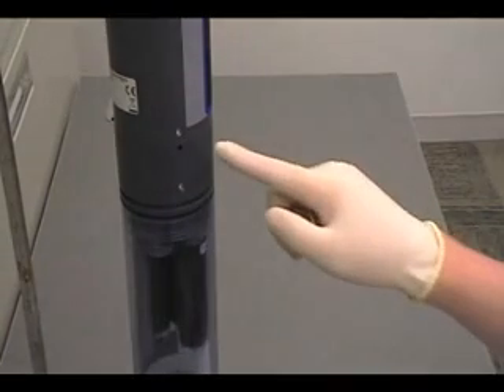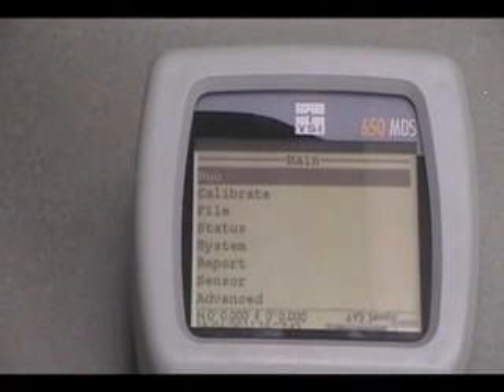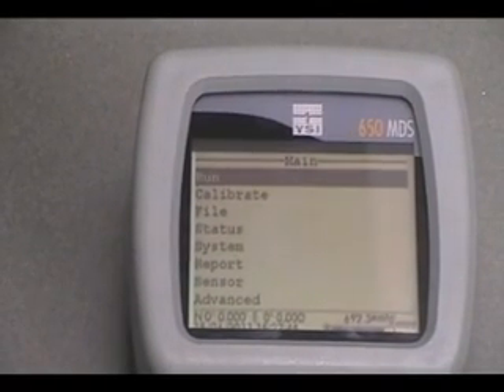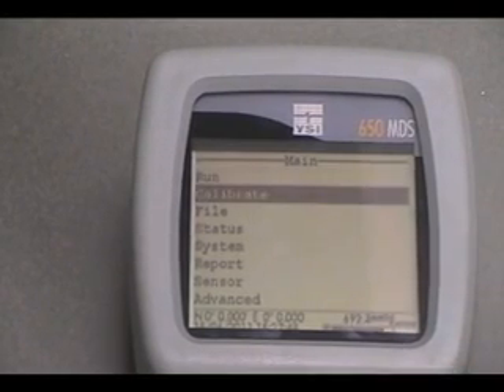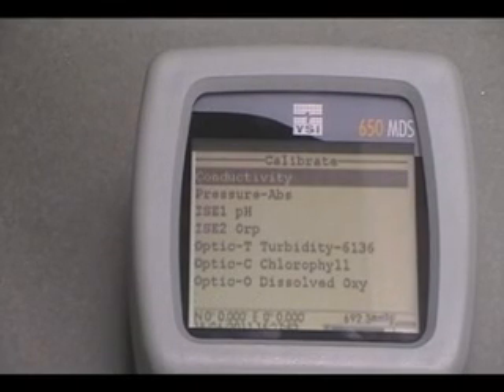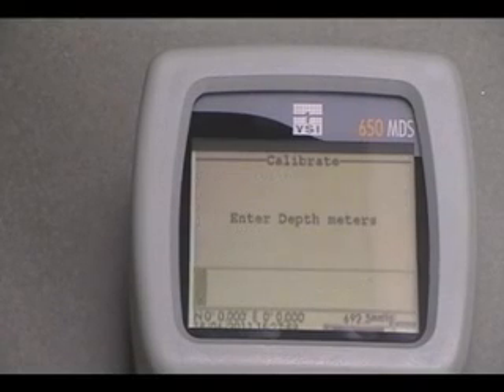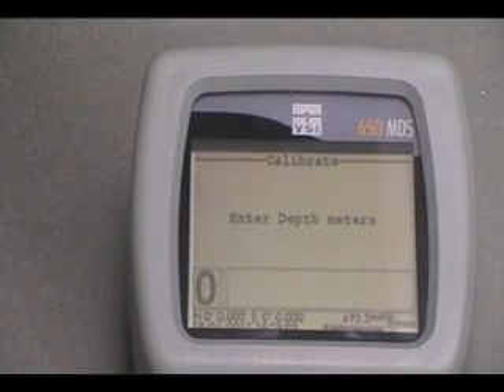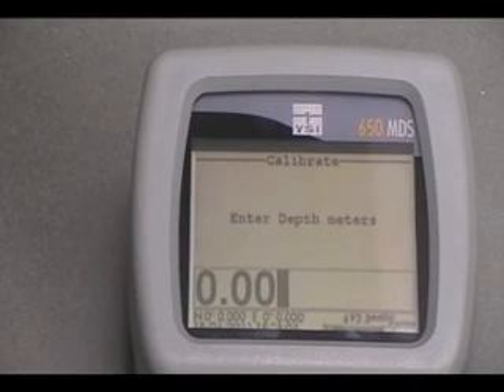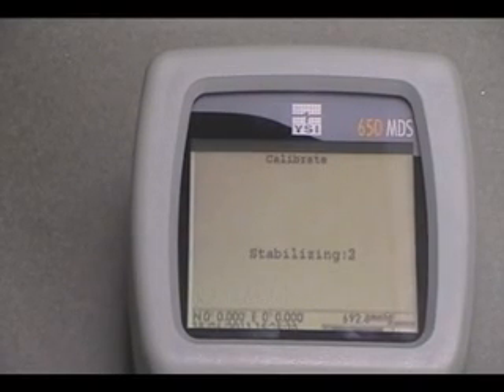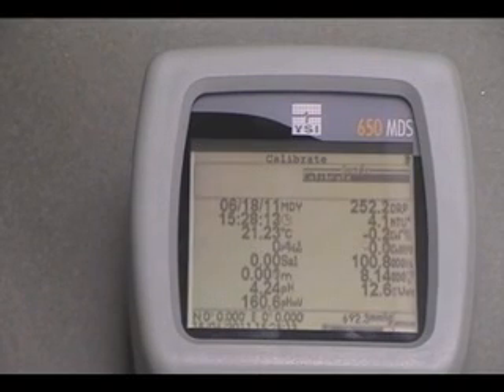Depth calibration. Step 1. Make certain the depth sensor is in air and not immersed in any solution. Step 2. From the Sonde menu, select Calibrate and press Enter. Step 3. Select Pressure ABS and press Enter. Step 4. Input 0.00 and press Enter. Step 5. Wait 30 seconds or so until the readings have stabilized.